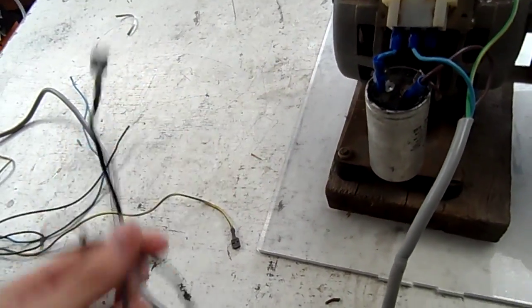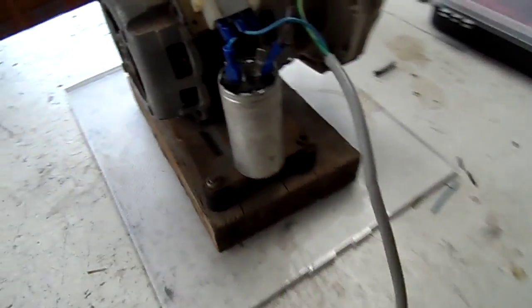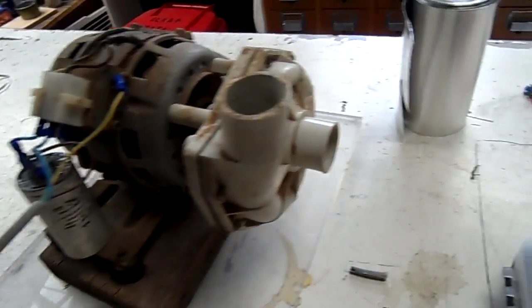It used to have that on it, so it's really not a very good idea, not very safe. But yeah, it's got an 8 microfarad 450 volt AC cap, so it's got a nice fast start.